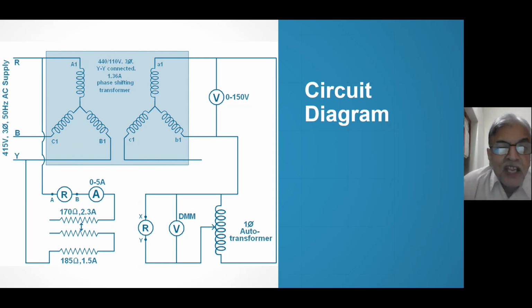If you see how many things you need, I think none of them are unavailable in your institute. Usually a phase shifter is available. For relay characteristics, a directional relay must be available, otherwise you'll have to purchase one. Apart from that, 170 ohm and 185 ohm rheostats are small things, usually available in the laboratory. A 5 ampere meter, 0 to 150 volt voltmeter is always available, and DMMs are available in the laboratory.